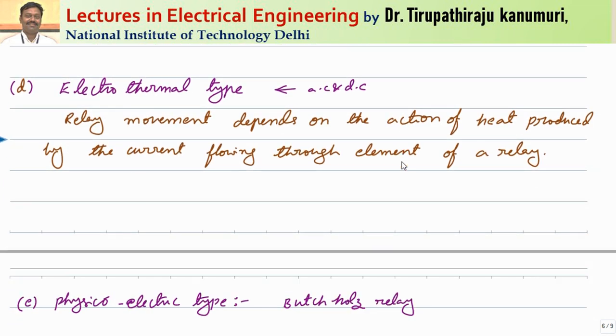Next is the electro-thermal type, which can be used for both AC and DC. As the name suggests, electric current produces heat. The relay movement depends on the action of heat produced by the current flowing through the element. Since heat is proportional to I-squared, it is based on the RMS value — that is why it works the same for both AC and DC.